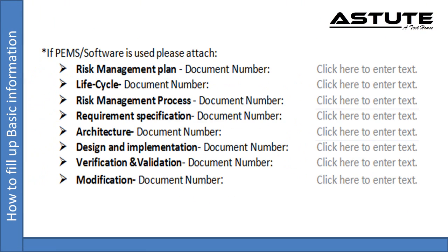If the equipment has software or is a PEMS, please provide us the software risk management plan, life cycle, risk management process, requirement specification, software architecture and design, implementation, modification, verification and validation.